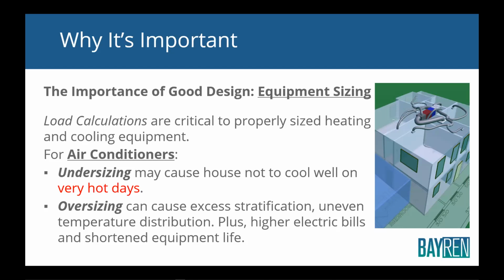Well, oversizing air conditioners will, and I can guarantee you this, cause more comfort complaints than if you were to undersize the air conditioner. And very few contractors realize that. But don't undersize, don't oversize, properly size. And the way to properly size is to do a load calc and size your equipment based on that load calc, okay?